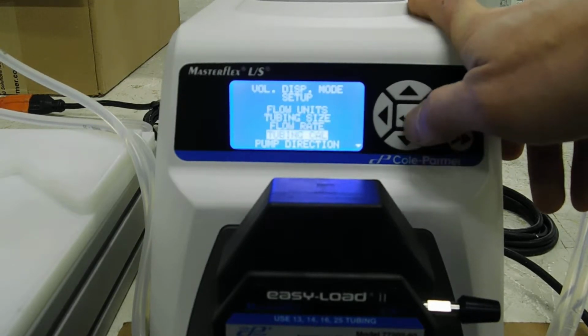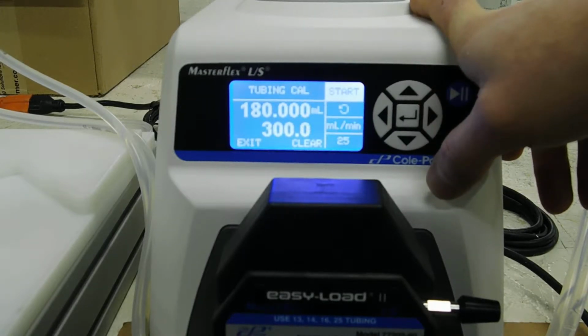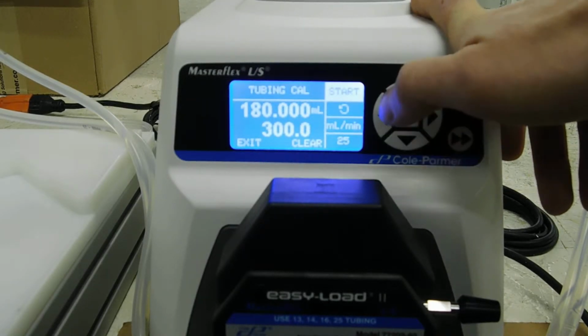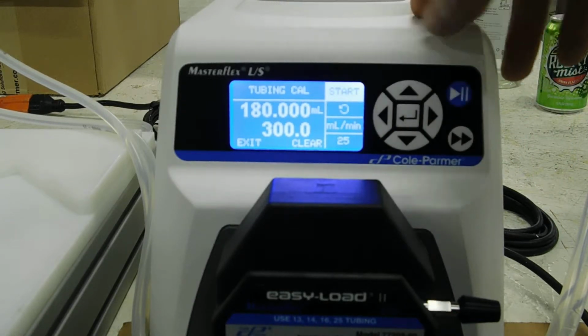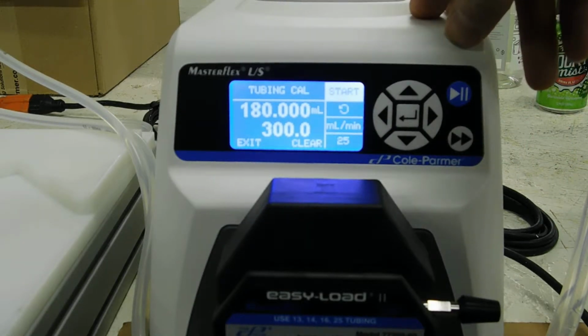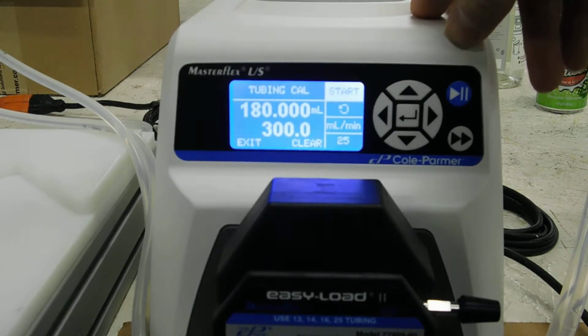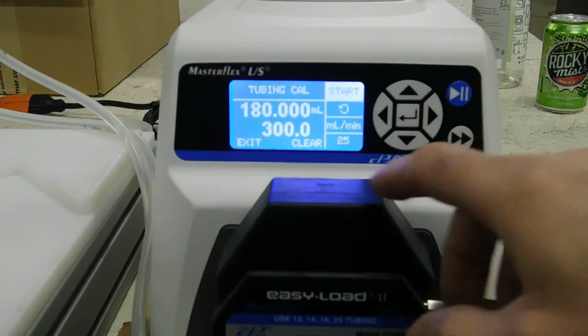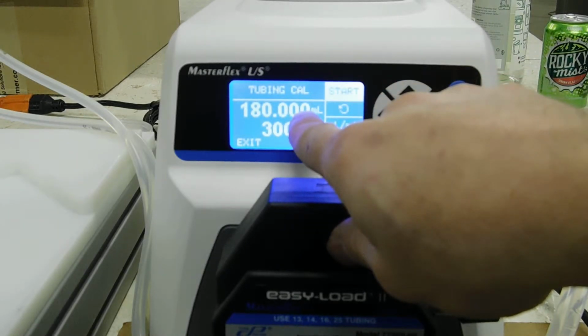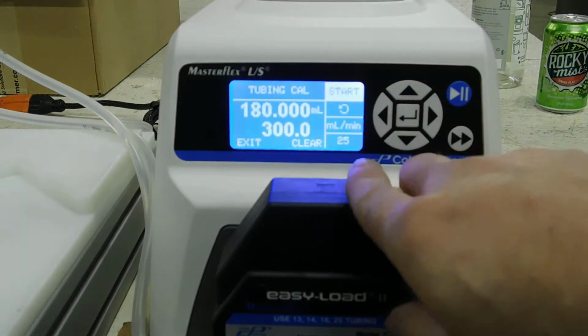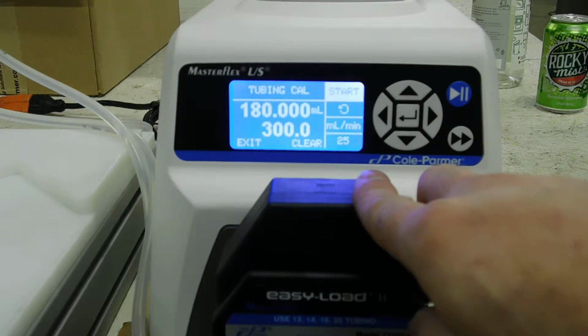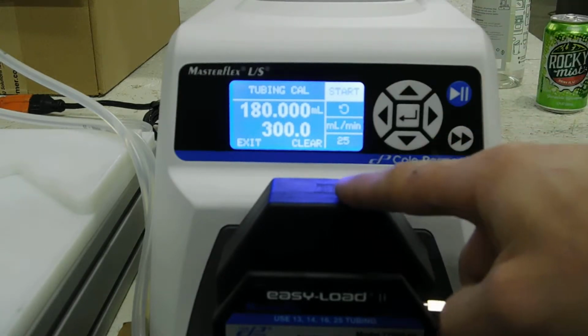From here, we can go into the tubing calibration. So for each tubing, you'll have to calibrate it. In order to get 30 milliliters of product, you'll have to calibrate the tubing. This is something you may have to do a couple different times until you get the hang of it, but basically for that size tubing, it's recommending that it dispenses 180 milliliters of product into an arbitrary container.